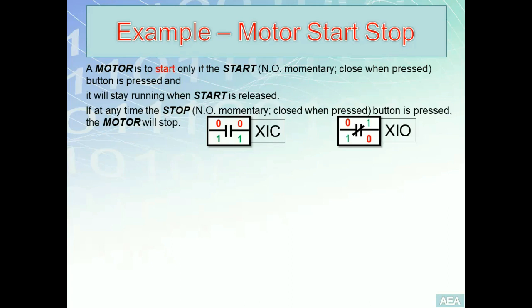The first term is 'start', which refers to the state of the motor — the output we want to achieve. The start switch is normally open, meaning it reads zero into the PLC memory when not pressed, and closes when pressed. It will stay running when start is released. The stop switch is also normally open, closed when pressed, and the motor will stop.